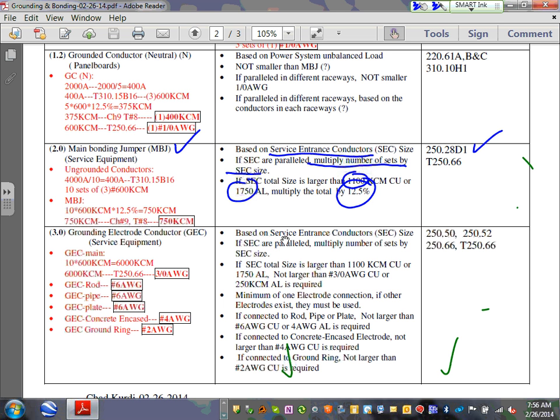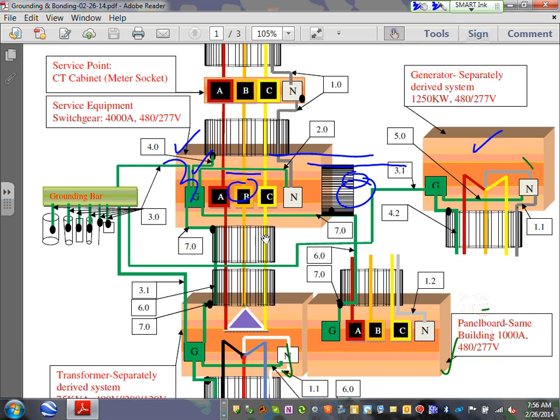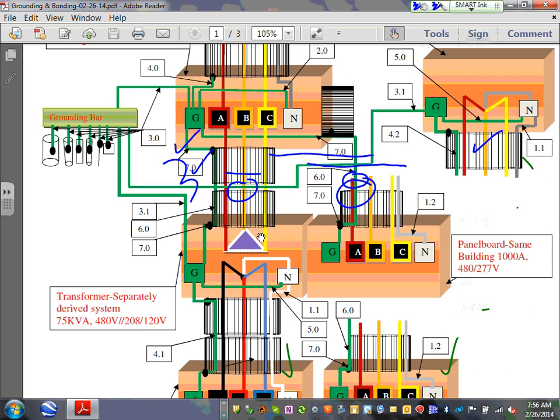Any comments, any questions? Everybody understand what a main bonding jumper is? You cannot just call it a bonding jumper, Adam. You have to call it main bonding jumper, right? You have to name it exactly what the code calls it. It bonds the neutral to the ground. Karen, I'm going to walk you guys through sizing it right here in a second. Can you guys see the sizing? Size and example. Okay, so that's my main bonding jumper. Let's keep going, guys, into the system and explain what the system is. Then let's go to 3.0.